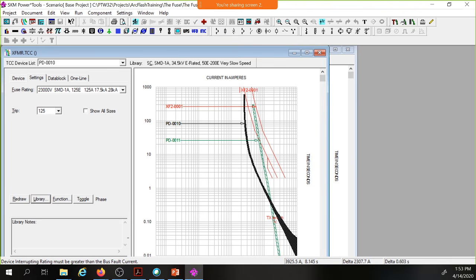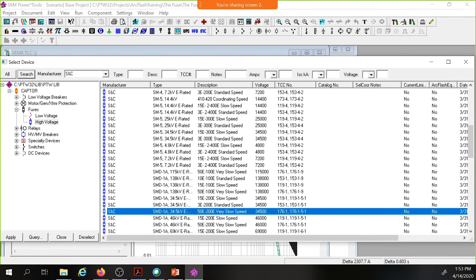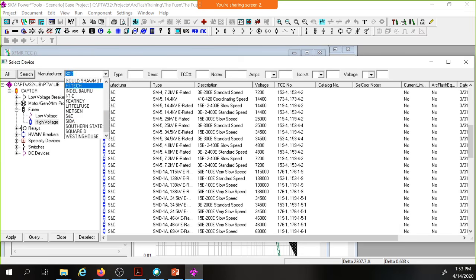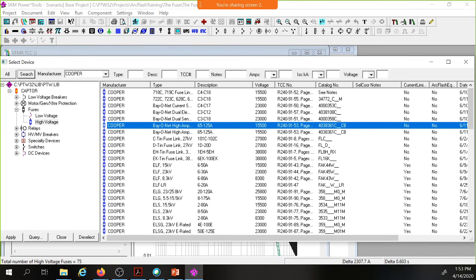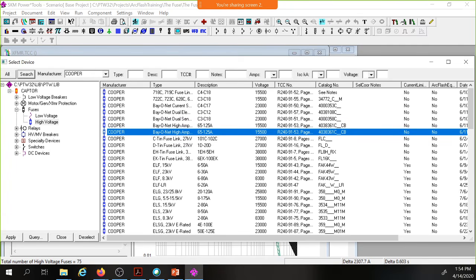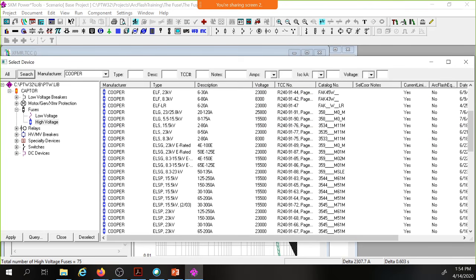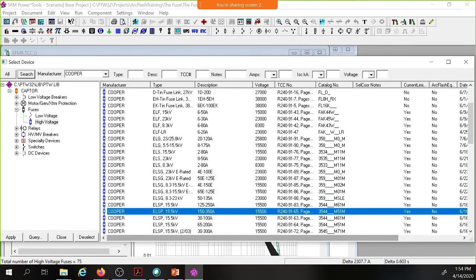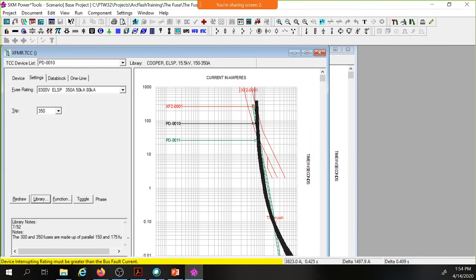So on the medium voltage side, you're picking a device, but you don't have to worry about this upper portion of that transformer damage curve, because that's your primary fuse that you're going to be using, is more for the short circuit protection capabilities than it is for the overload on that transformer. So you're not necessarily worried about that upper portion. You're more worried about the capabilities of the short circuit nature of that fuse.